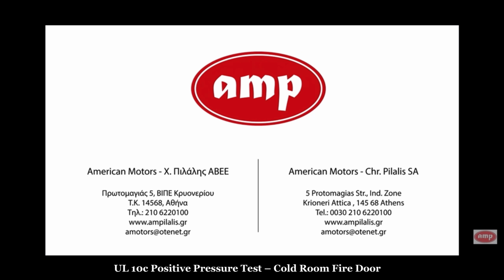What we just saw was the UL 10C fire resistance test. And in order to pass the UL 10C, the door assembly must do three things. Number one, resist fire for its rated time, 1 hour, 90 minutes, depending on its rated time period. Number two, do it under positive pressure conditions, because this simulates real life conditions. Number three, survive the hose stream test after the fire exposure. So when you see UL 10C on a fire-rated door label, it means that door was tested under the most realistic fire conditions and passed. So basically, UL 10C is the gold standard for making sure the fire door will actually perform the way it's supposed to when a real fire happens.